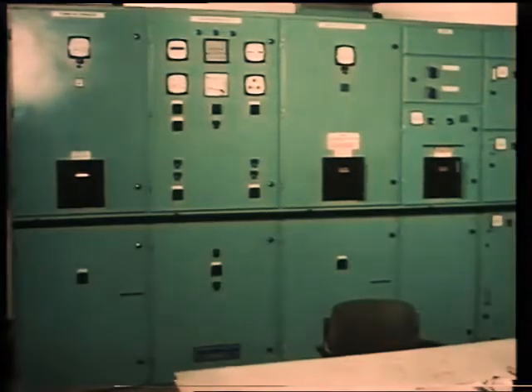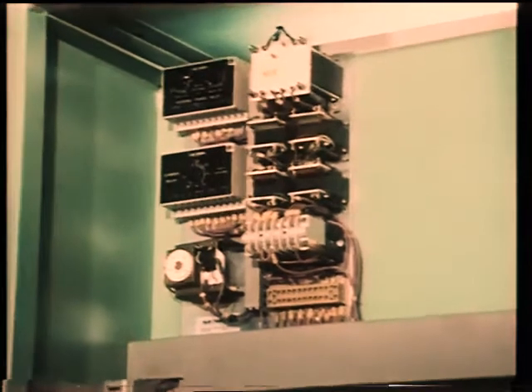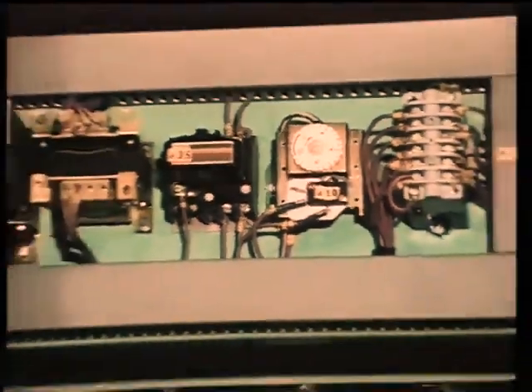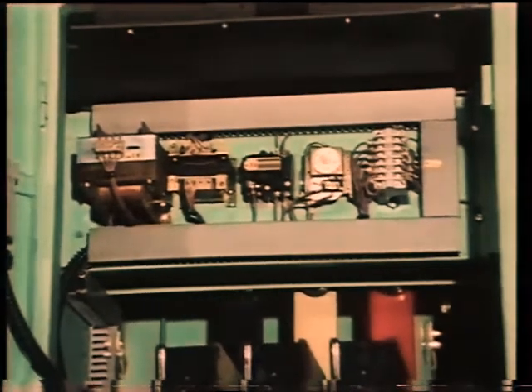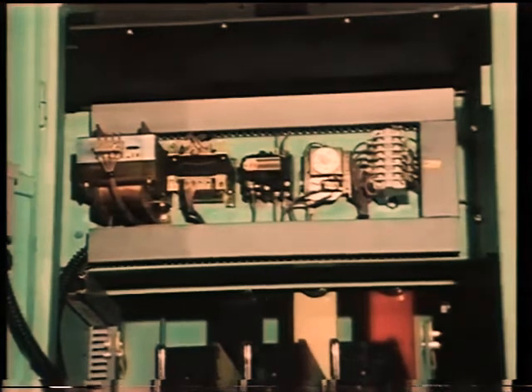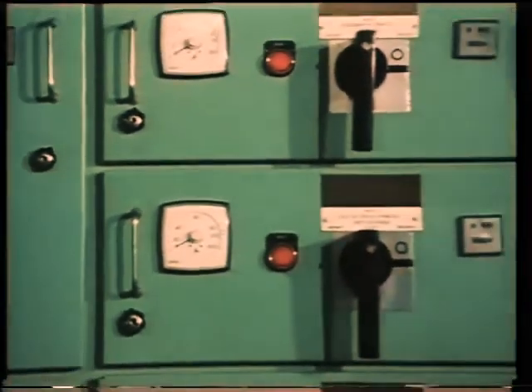The main switchboard will also contain the reverse power relays, protecting each alternator while running in parallel. Also, a preferential trip system is usually provided for tripping non-essential loads in case the demand for power is greater than the connected alternator or alternators can safely provide. Several panels on the main switchboard will contain group starters.